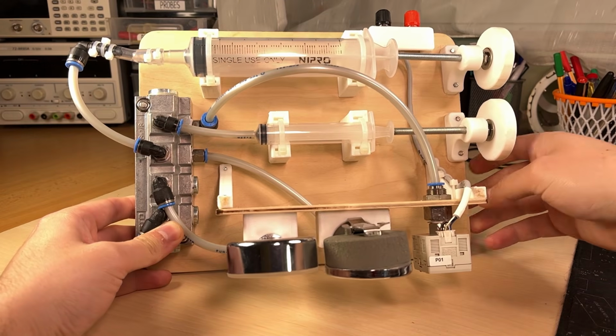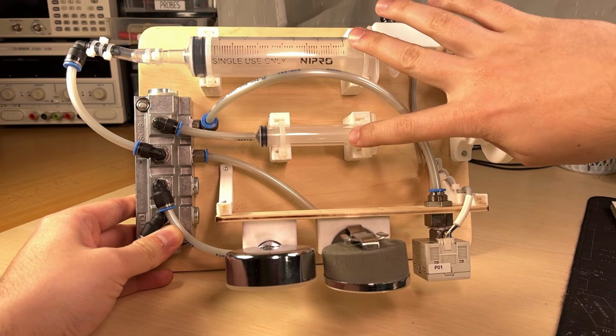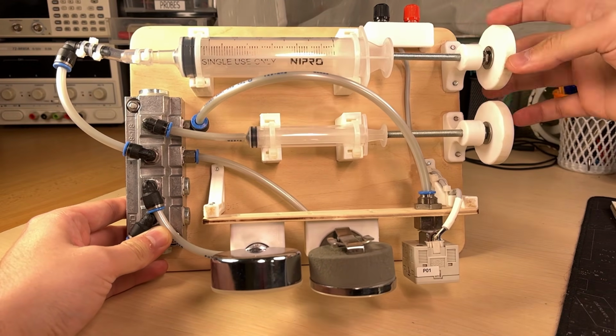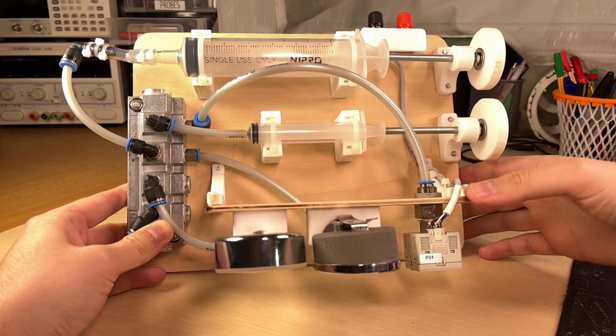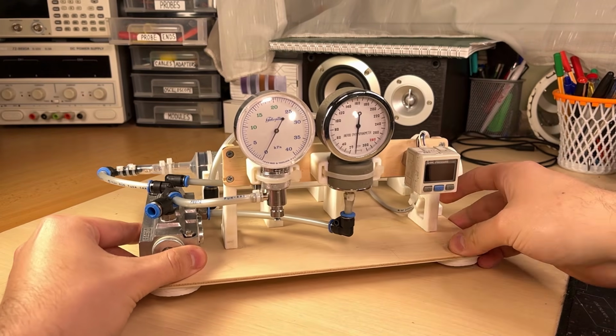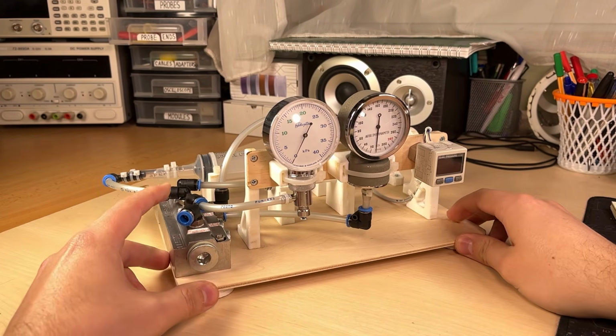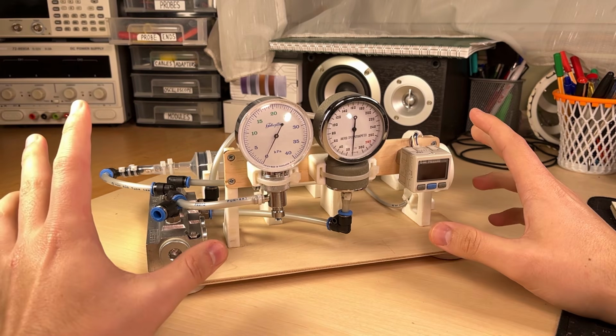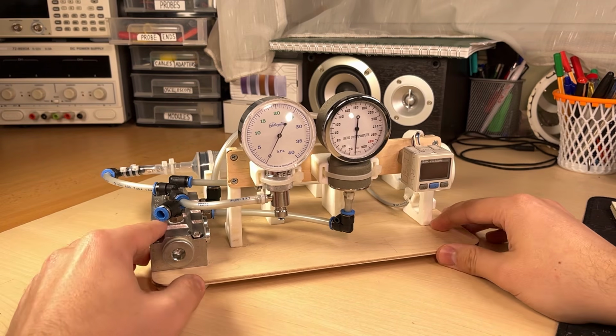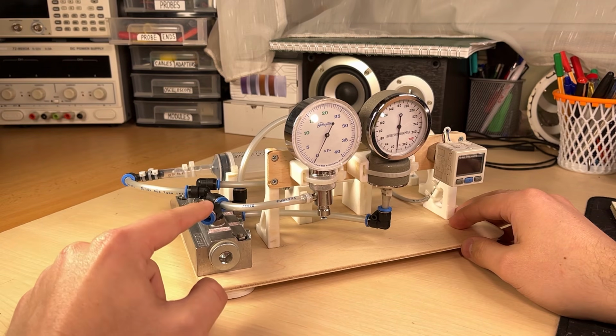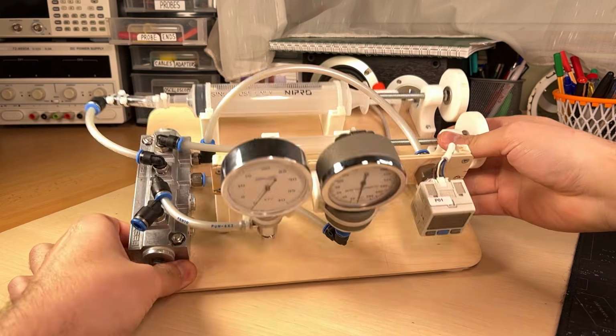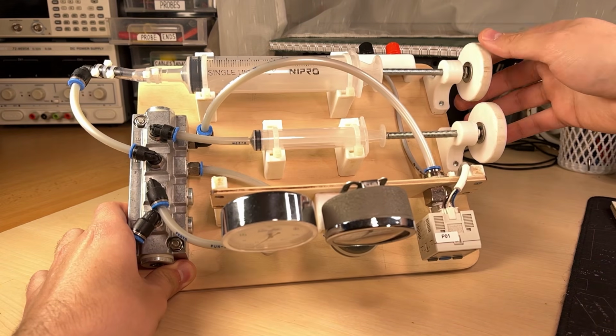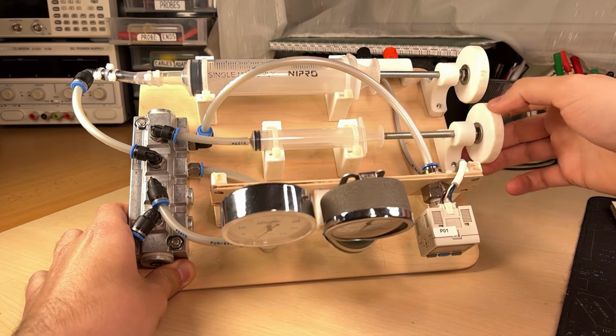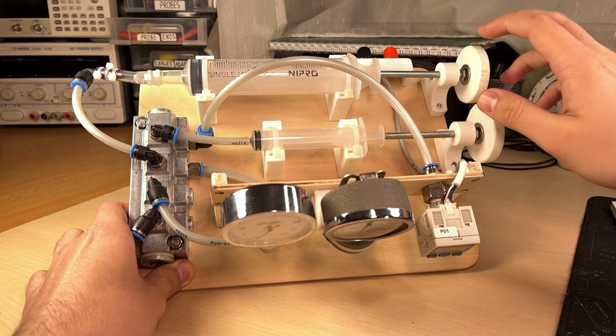Now, as you can see here, it consists of two syringes, which you can adjust using these hand screws in the back, and it has 3 pressure sensors with this manifold right here. So how this works is actually you connect the pressure sensor to this port right here, and you increase the pressure in the system and keep it at a constant level using these screws here.